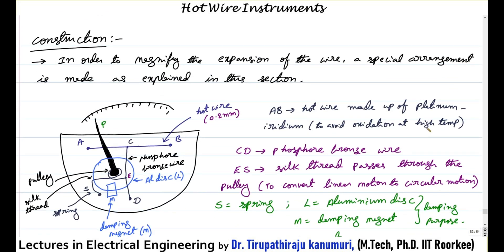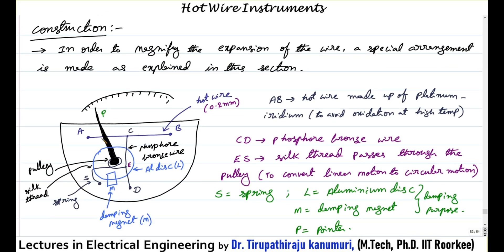Let us see the practical construction and how this is amplified. In order to magnify the expansion of a wire, a special arrangement is made with a scale, pointer, and pulley. From point A to point B, the hot wire is connected. This hot wire is made up of platinum iridium material, because this material is free from the problem of oxidation even at high temperatures.